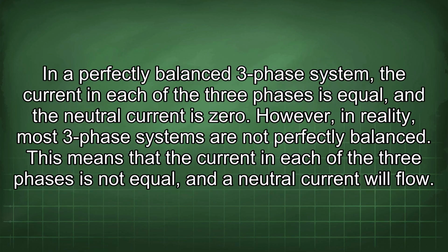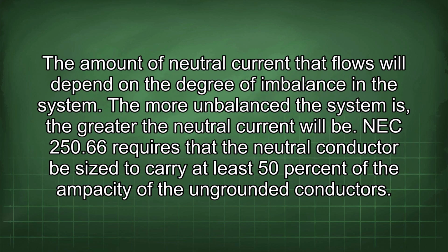In a perfectly balanced three-phase system, the current in each of the three phases is equal, and the neutral current is zero. However, in reality, most three-phase systems are not perfectly balanced. This means that the current in each of the three phases is not equal, and a neutral current will flow. The amount of neutral current that flows will depend on the degree of imbalance in the system. The more unbalanced the system is, the greater the neutral current will be.